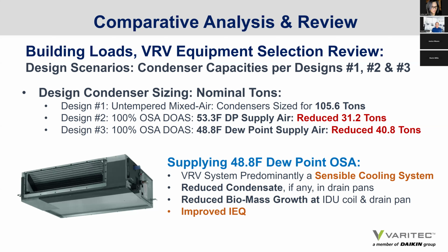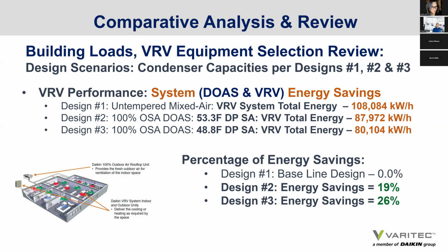So, supplying 48.8 degree dew point on your DOAS system means that, and I'll never forget this conversation with Judy Peters of Daikin when she was running through the results with me. She said, "Holy cow, Dan, when you provide 48 degree dew point from your DOAS unit, that turns your variable refrigerant system into a sensible cooling only system." Which means that really what you have is almost a refrigerant chilled beam. Now we don't have drain pans filling up with water, adding humidity to a space we're trying to provide humidity control to. We don't have biomass growing within the condensate pans. Consequently, you have an element of improved IEQ to a building.